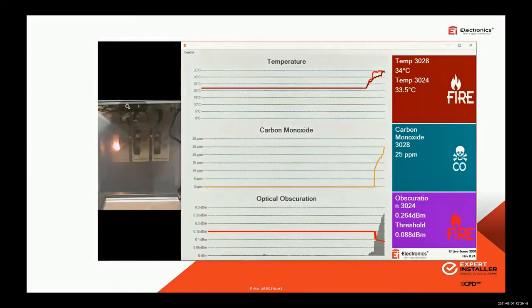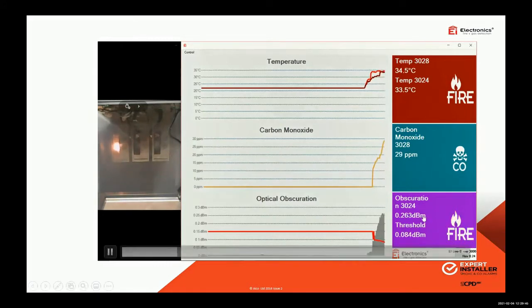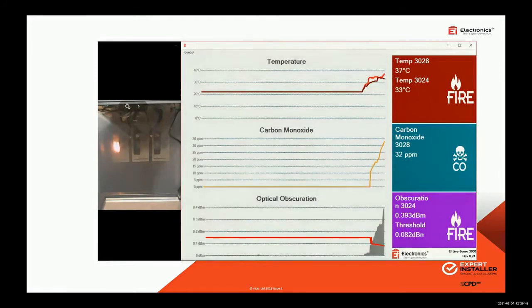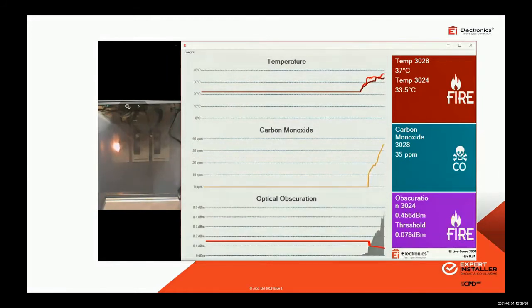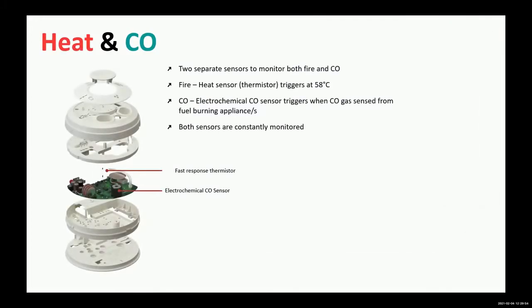So it's faster reacting than any other device on the market, and doesn't have any of the false alarms because of the intelligence and the dust compensation that's built into the unit itself. The next one we're going to have a look at is the Heat CO, and this is a nearly new unit, not long on the market, about 6 or 8 months. It's a combination of heat and CO. There's no intelligence built into this. It's just 2 separate sensors under the one cover, basically. Okay, so you have a fire sensor again with the threshold of 58 degrees C, and you have the electrochemical CO sensor, which triggers when there's carbon monoxide present. And both of these sensors are constantly monitored.